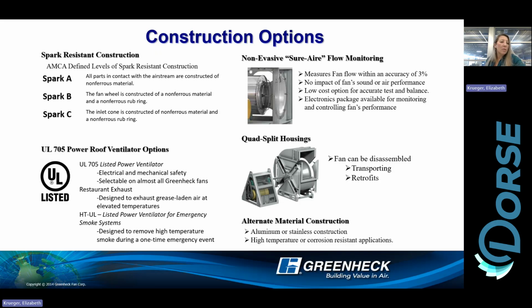With the other UL listings we offer on the USF, we have restaurant exhaust available. Applications for restaurant exhaust can sometimes get to be high pressure if they're using a pollution control unit. If you have a big bank of filters filtering the air, or a scrubber, the USF is an excellent choice, because if those filters start to clog, maybe you're seeing 5 inches of static pressure through those filters in order to maintain the same CFM.